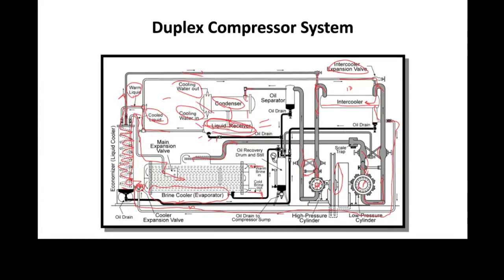All right, so in this way, we both increase our net refrigerating effect, and we have all of the beneficial effects of a multi-stage intercooled type of system.